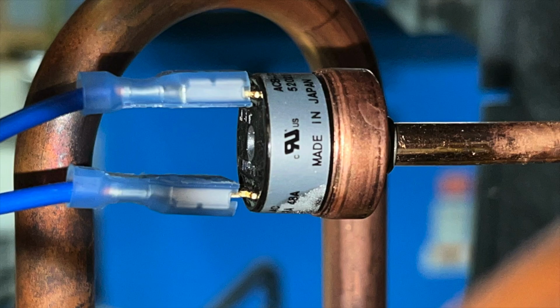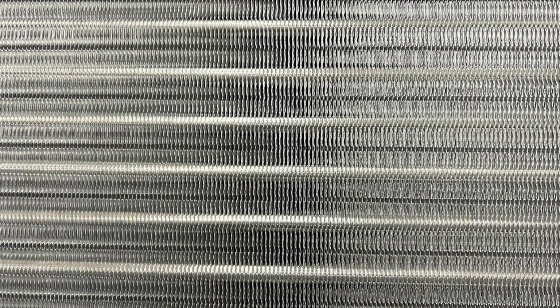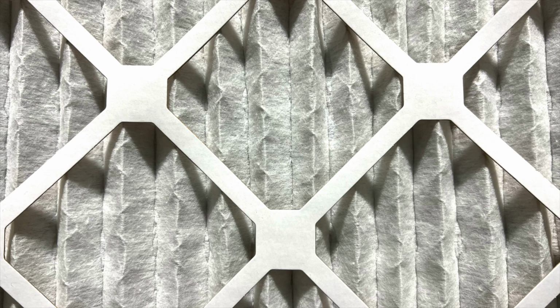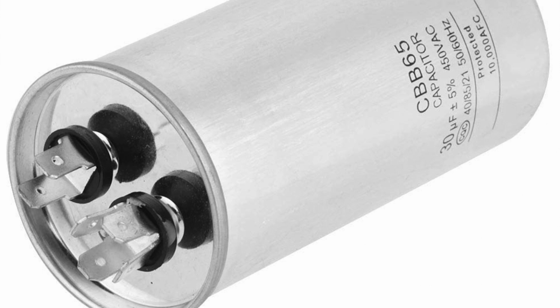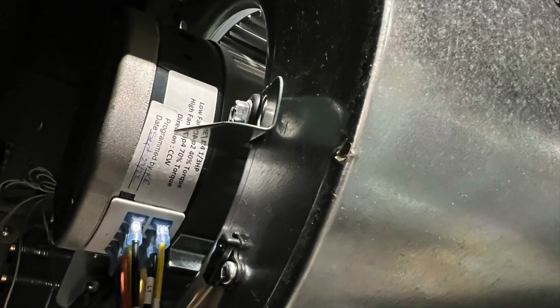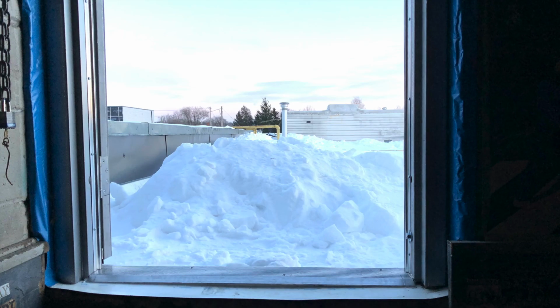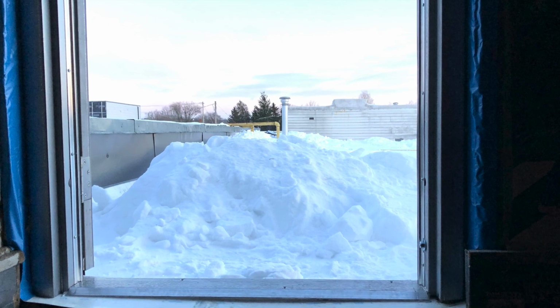Check for continuity at the low pressure switch. It should be on at a standing pressure of 180 psi. If standing pressure is low, then check for refrigerant leaks. If standing pressure is good, reduced or restricted airflow might be the culprit. Check for coil cleanliness, air filters, fan capacitors which might control speed, fan taps, and rotation of the fan motor. Return air that is too cold might be contributing to the problem.